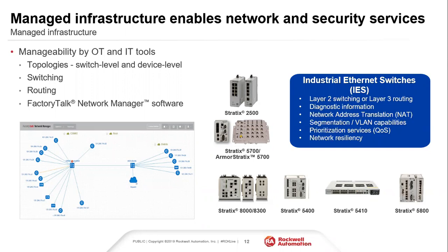The ability to do switching means you can now support multiple IP addresses or different VLANs, different subnets. A lot of the time what you might see is your DCS is a 172 dot address range, and your power equipment might be a 192 dot address range. If you want to still have that segmented, especially in the past, you had to have different switches for each environment and then home run everything back. Now we can take one switch, do that segmentation, consolidate everything into one switch, and then trunk that cable, so that one Ethernet cable going up has the ability of swapping between the two.